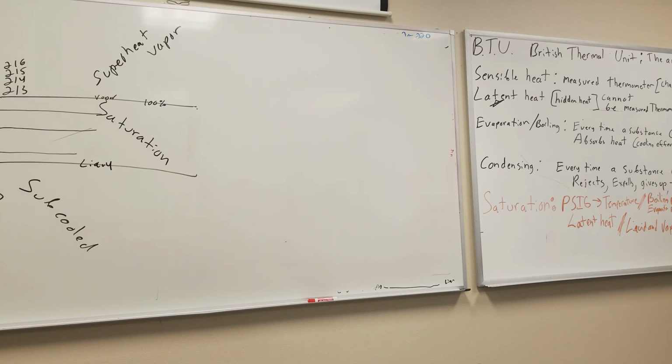But now, if it was at pressure, let's say, just throw a number out here, 100 psig, so 300, and that water's actual temperature was 72. So 300 minus 72? 228. 228 degrees subcooled liquid. By changing the pressure, I change the boiling point.